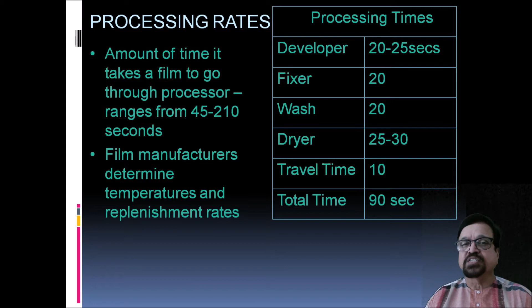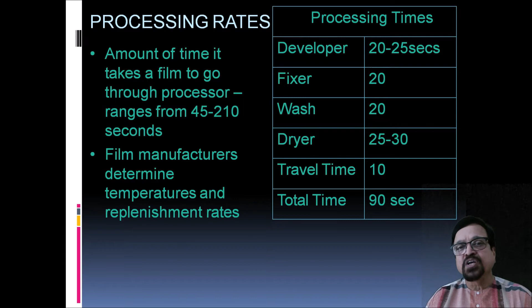Approximate times are given for developer, fixer, washer, dryer, travel time and total time. So it is significantly reduced as compared to manual processing. The amount of time it takes a film to go through the processor ranges from 45 to 210 seconds, and that can be set manually on the automatic processor. Film manufacturers determine temperature and replenishment, and often it is done once the first film comes out. You can view a film and find out where the processing time is required more or less.